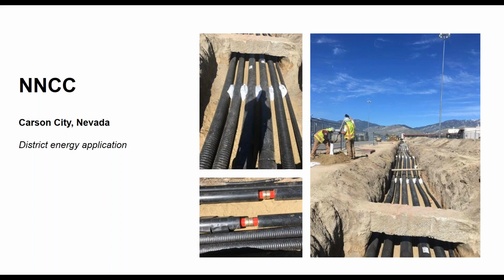This is a federal penitentiary in Nevada. The objective was: we've got an existing penitentiary that we're not going to idle and move inmates out of, they need to stay in place, but we need to be in and out as quickly as possible. We want to minimize the time trenches are open, and bring all the mechanical into a central location so it can't be interfered with - no open chases or ducts for potential inmate escape. The objective was to run heating hot water, chilled water, and domestic water all in a common trench, picking up multiple buildings.